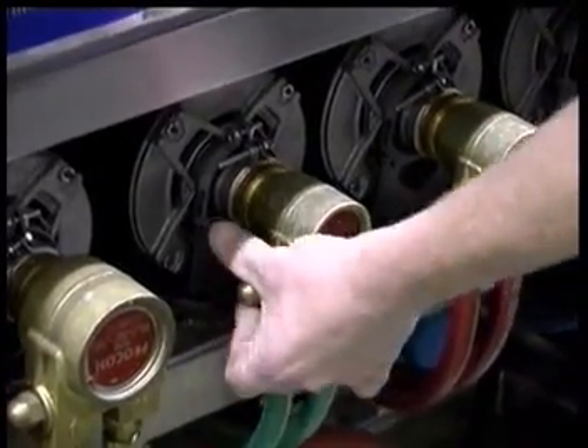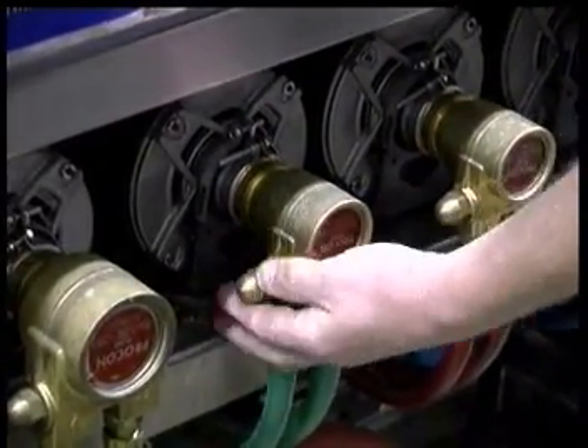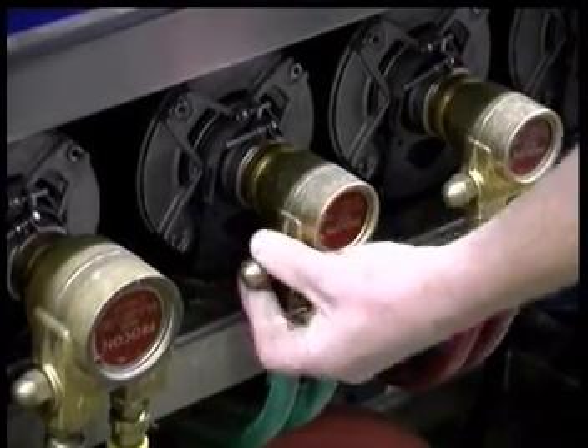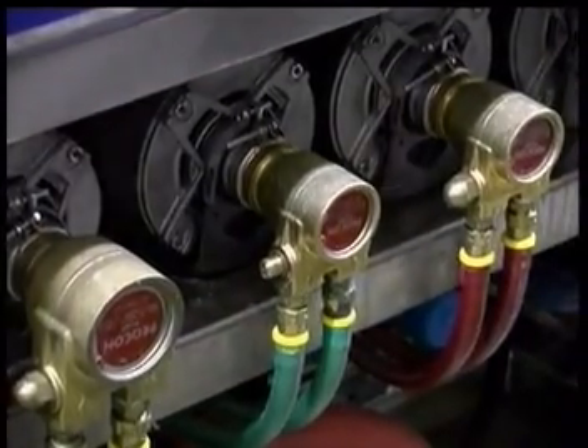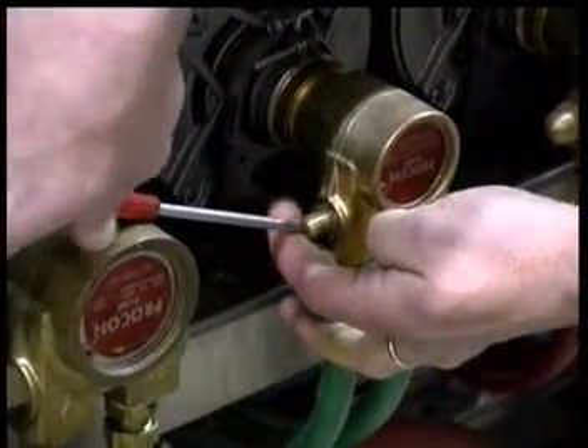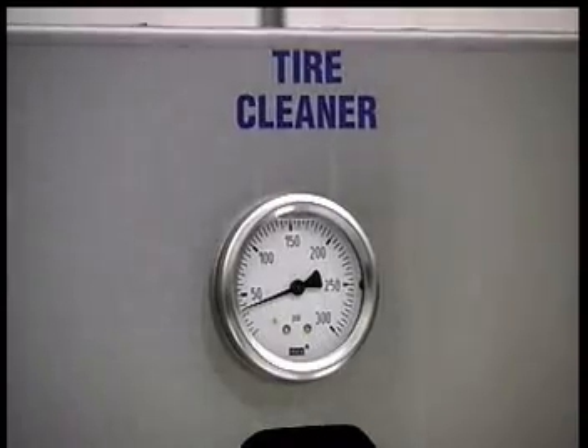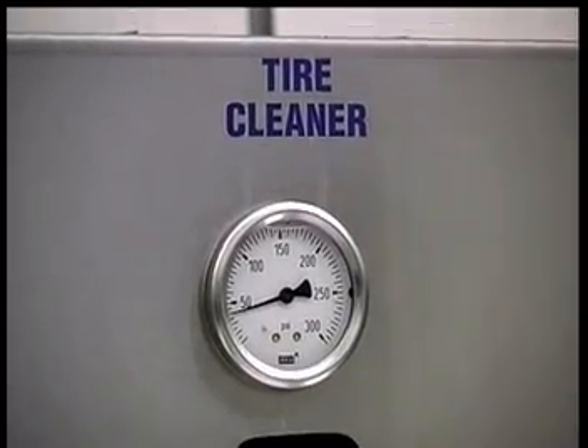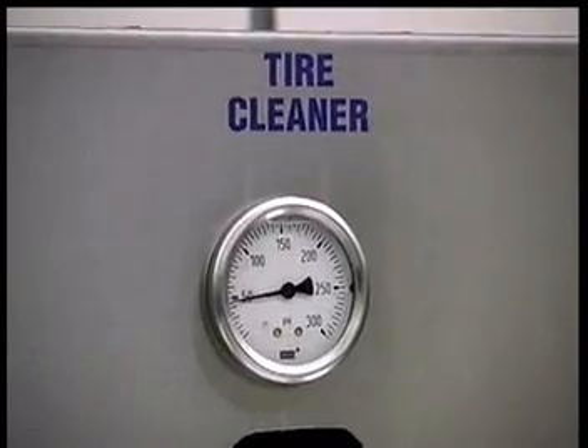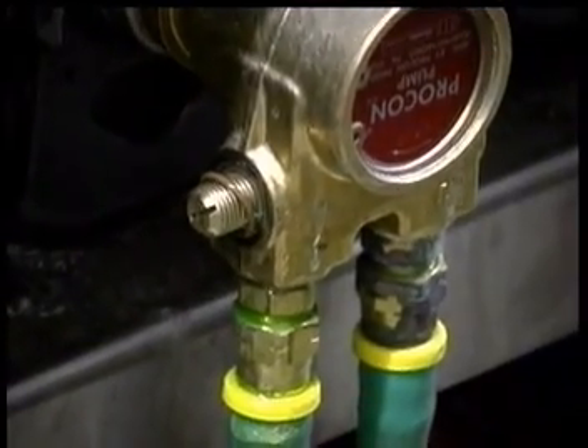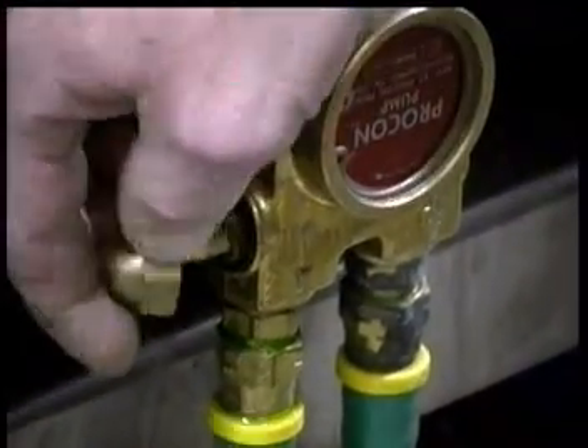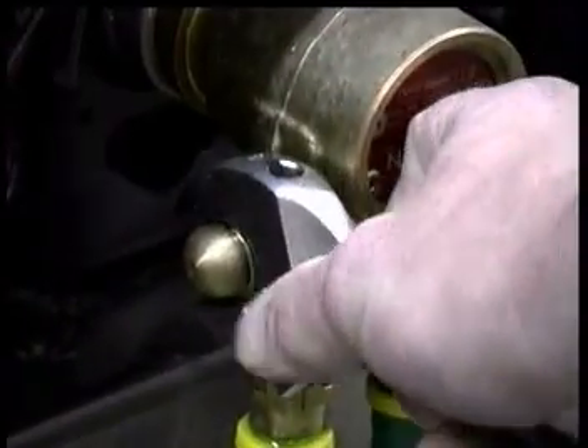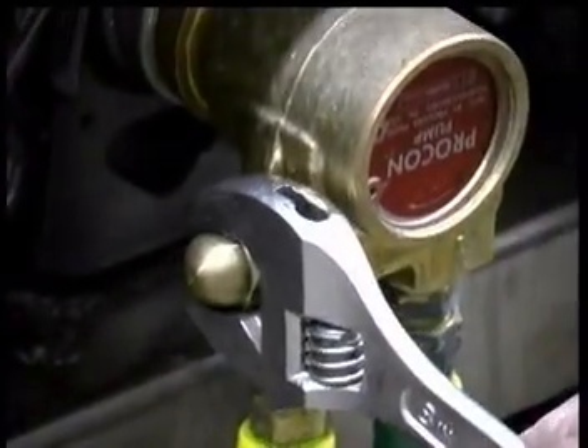To adjust the pressure of the Procon pumps, remove the cap nut to expose a threaded adjustment screw. Using a flat blade screwdriver, turn screw clockwise to increase pressure. All pressure adjustments should be made while the pump is running and product is flowing. While the cap nut is removed, it's common for a small amount of product to leak. The cap nut includes an O-ring designed to seal off the adjustment screw.